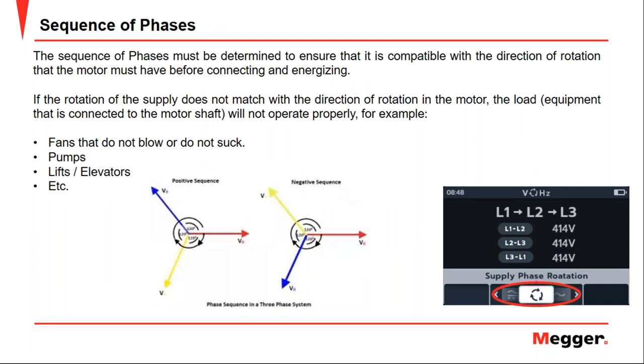Okay, before connecting the motor, we must identify the phase sequence of the power supply to make sure that the motor is going to rotate in the direction that the load requires. If the rotation of the supply doesn't match with the motor rotation, the load equipment that is connected to the motor shaft, whatever it was, will not operate properly. For example, if we have fans, we have to do this verification because it's very important for the functioning of the fans. The same with the pumps. Lifts, elevators. So this is a very critical issue for some of our applications. So it is very important to know what the sequence of phase is in our application.